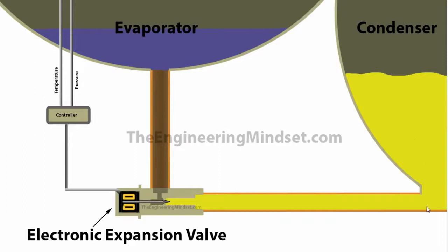So that refrigerant in the condenser flows along the liquid line into the base of the valve. The controller is sensing that more refrigerant is required in the evaporator, so that sends the signal to the stepper motor just to pull that valve head back slightly and allow some refrigerant to start flowing. That refrigerant then flows off into the evaporator, and then at the maximum demands, the stepper motor has been moved and rotated the complete rotation, and that has pulled the valve body back, allowing the maximum amount of condenser refrigerant liquid here to flow off into the evaporator, and it will modulate back, changing the position of that motor and the shaft position to very accurately control the amount of refrigerant flowing into the evaporator.